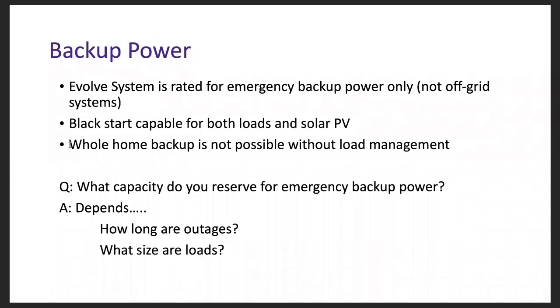So managing expectations and building a backup loads panel with essential loads in the off chance that the grid goes down. How often does the grid go down and for how long? In most cases, usually it's short duration. Most cases not longer than a few days, and essentially you want to keep the food cold, keep the lights on, and have the ability to communicate and survive comfortably without the grid voltage. So anyways, management of expectations. So as an exercise, the question here is, what capacity would you reserve for emergency backup power?